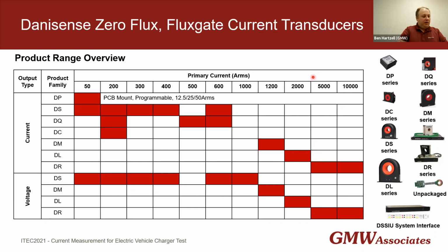And then the transducers with the burden resistor built into the transducer head are all the ones of 2000 amps or lower. The larger ones have a separate electronics box, so a rack mount electronics, and the measurement is taken out of there instead. And there is also a DSSIU, which is the system interface unit. It's a 4 or 6 channel rack mount unit, which handles all your power supplies for all your transducer heads, as well as helps organize all the signal cables. And then also there's an unpackaged version of transducers available for OEM applications.